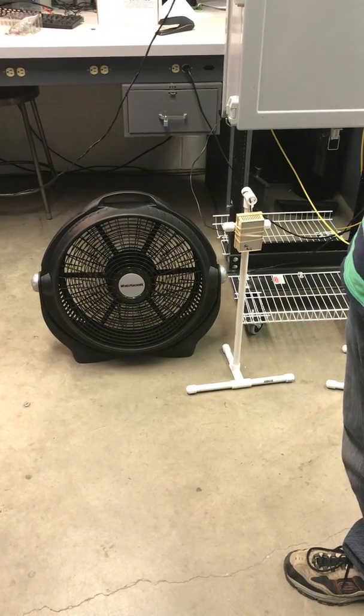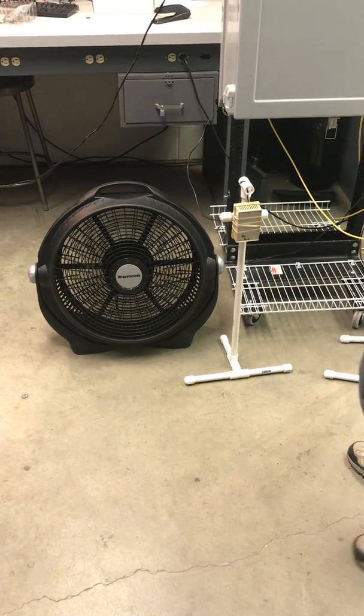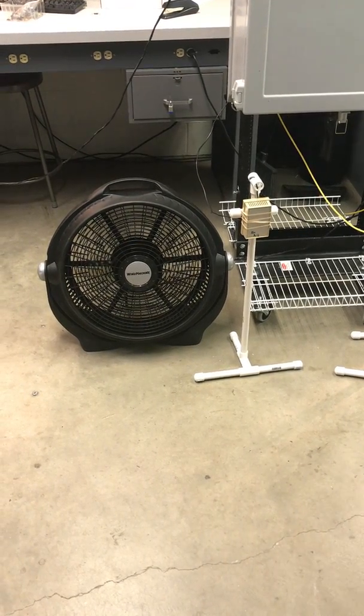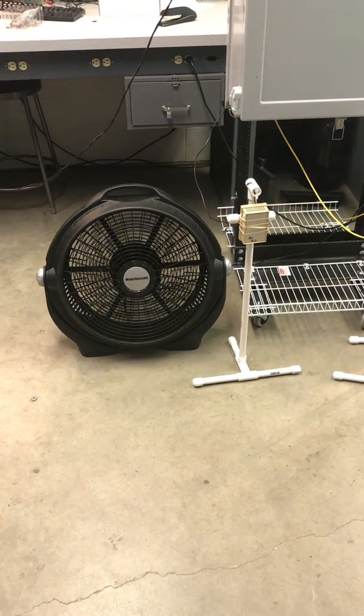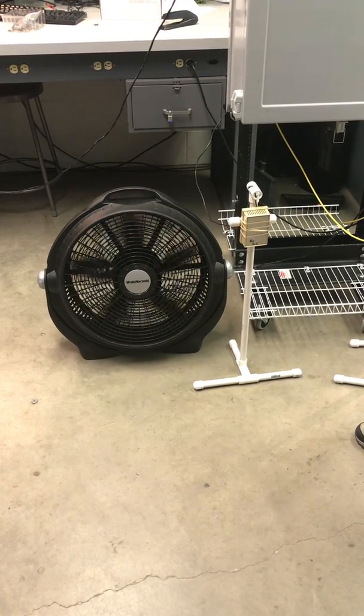And we'll monitor the internal temperature. Right now it's dropping, it's at 76.4, and it'll soon be below 75.5, and the fan should kick off at that point as long as we have motion in the room. So as you can see, the fan did go off when the temperature dropped.